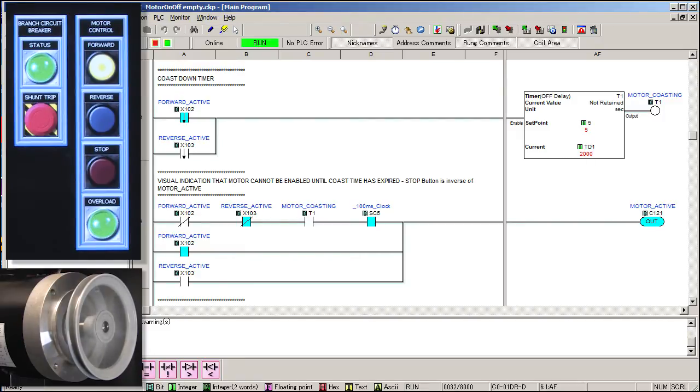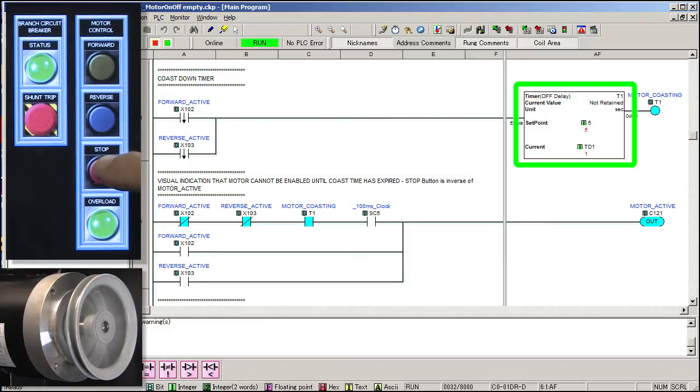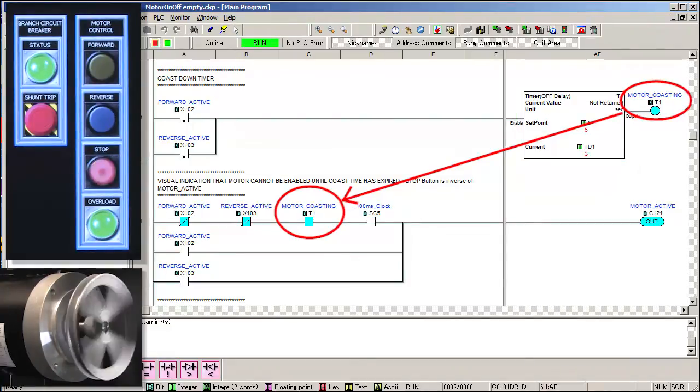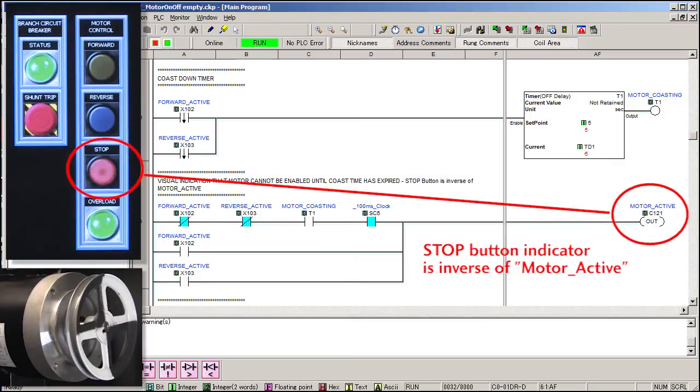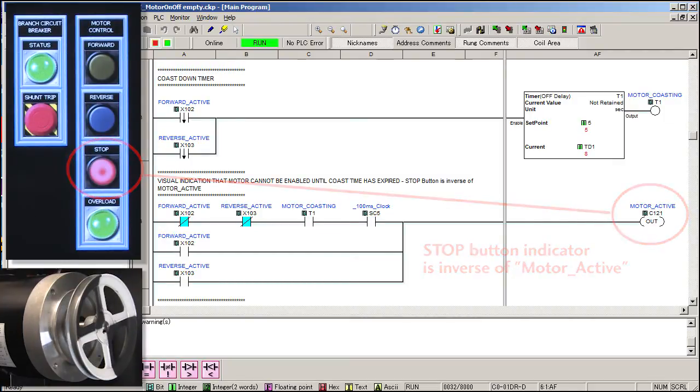Let's try it. When we press the stop button, the timer counts down, the motor coasting bit goes active, the AUX contact releases and sure enough, the stop button indicator flashes, perfect.